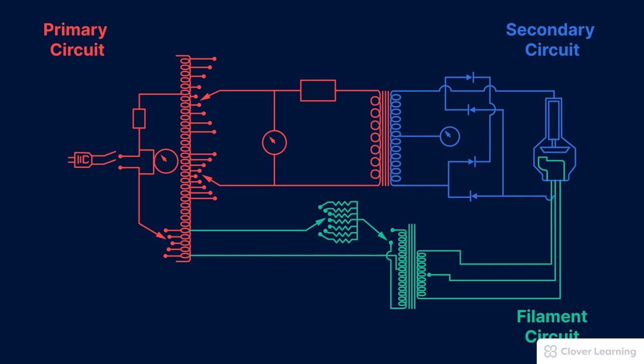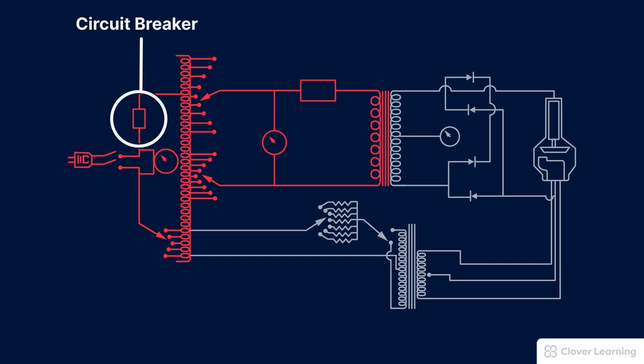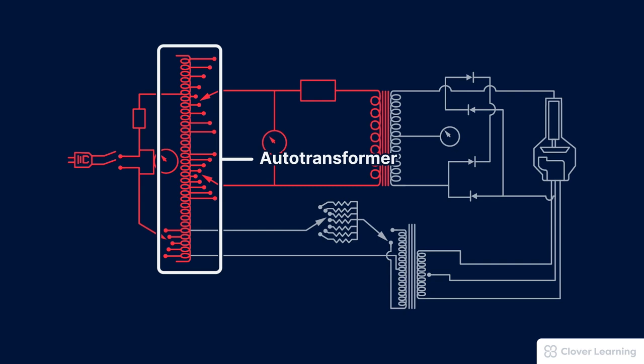The primary circuit receives the main power supply, and it also contains several components related to the voltage. The primary circuit includes the circuit breaker, which helps to protect the machine. The primary circuit also includes the auto transformer that we use to select the desired KVP.